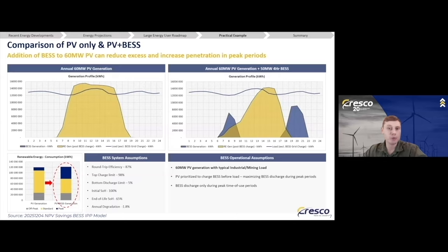But on the left-hand side with PV only, you can see the familiar pattern: strong midday generation, but a significant portion of that energy is excess, so above the load line. And on the right-hand side, when we add BESS to the system, the excess midday PV is captured and shifted into the morning and evening peaks, and you can materially increase your renewable penetration during peak periods.